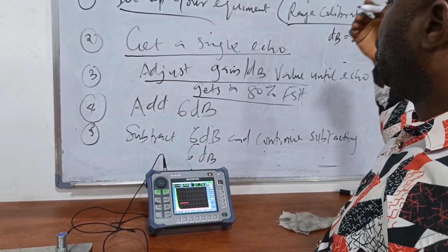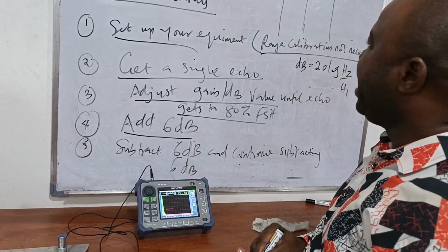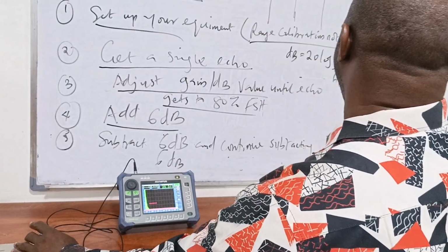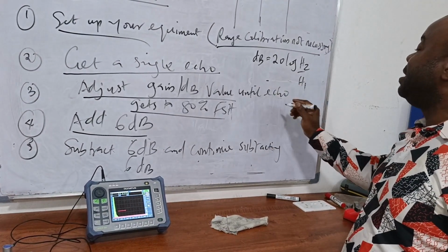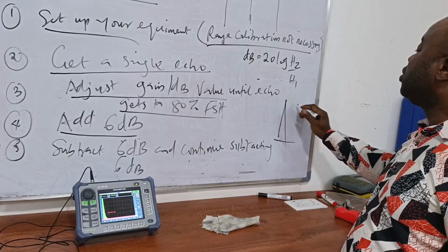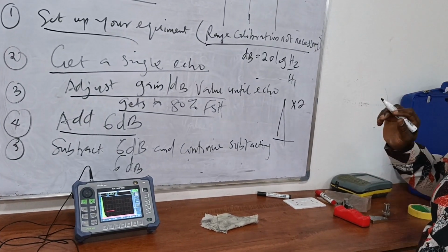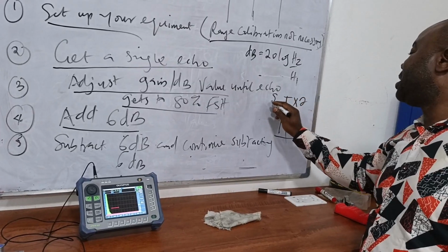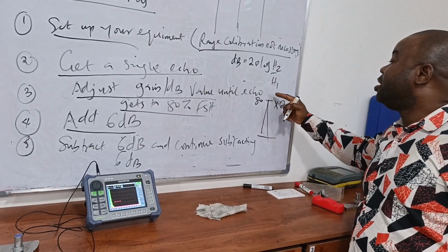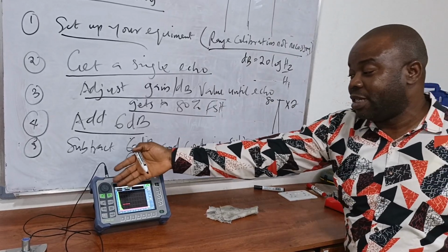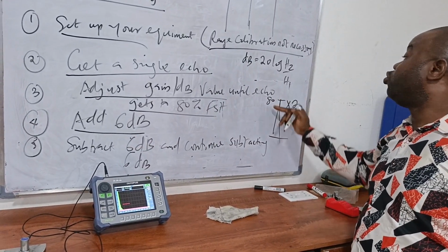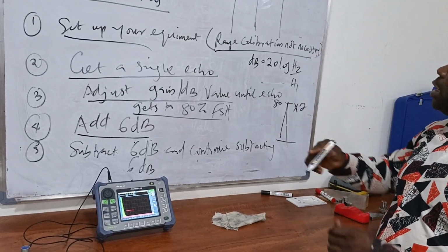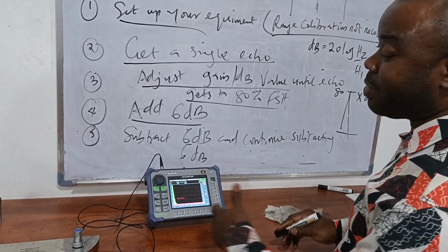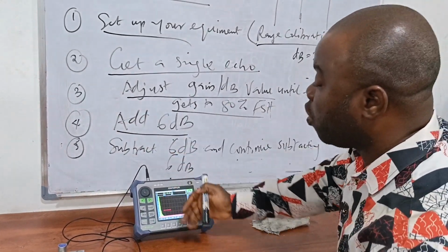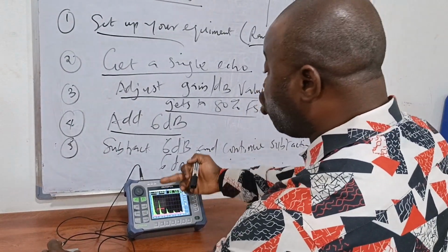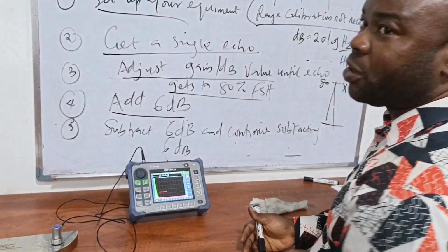Afterwards, you add 6 dB. If it is at 80% and you add 6 dB, the rule says that if I add 6 dB to any echo, the echo height will increase by 2. So if it is at 80% and I add 6 dB, this echo will jump to, of course, our screen is 100%, but in the literal sense, it will jump to 160. So what this first one does for you is to confirm that by the time you increase it by 6 dB, your echo should go above 80% of the first response pattern.